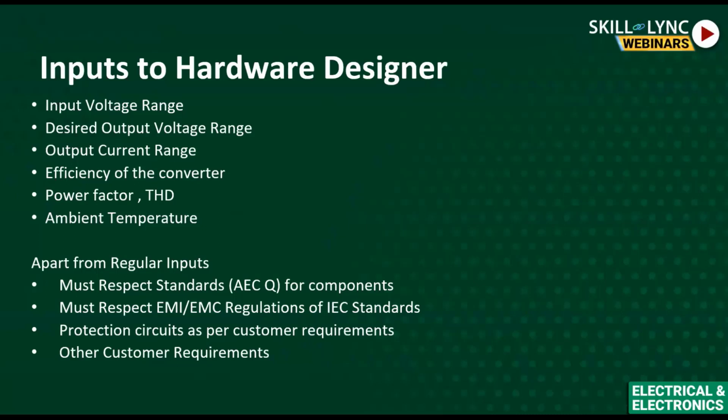The output current range is mentioned, and the efficiency of the converter is usually mentioned by the customer. Power factor is very important, and THD is very important. These two factors are decided by input stage 1. That is where stage 1 comes into the picture. So the input rectifier is important to shape the line current and to determine the power factor and the THD. Then there is the ambient temperature and the conditions under which the converter would operate.